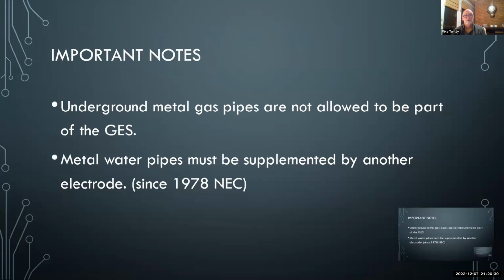Start driving ground rods. When I said earlier that a driven rod had to prove that it was less than 25 ohms to the earth, and if you need a second rod where it's not, they won't allow the water pipe to be that supplement. Even if you got a metal water pipe, you tie to it and then you drive two ground rods, you still got to have two ground rods.